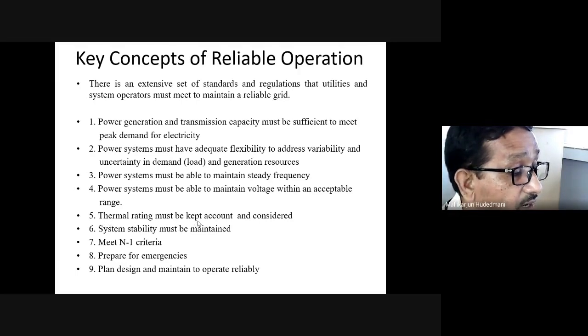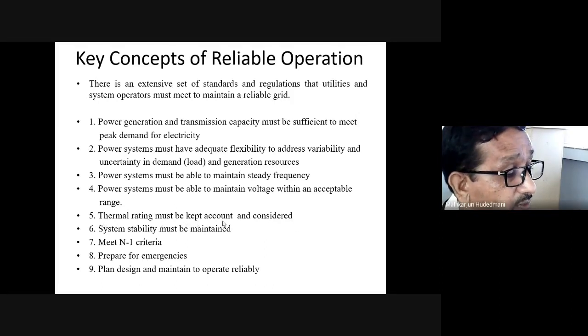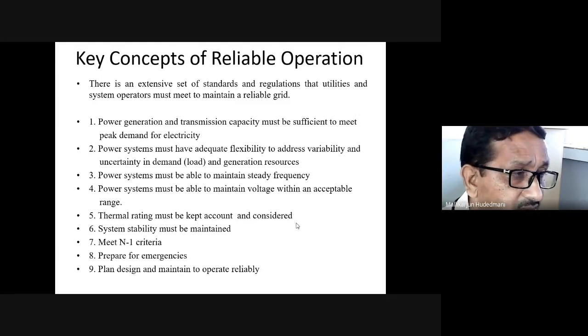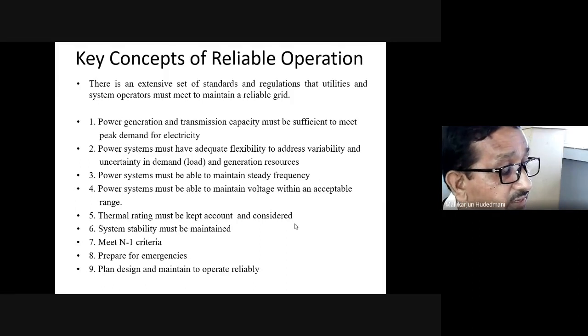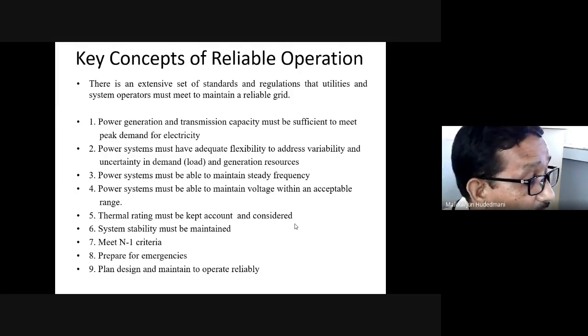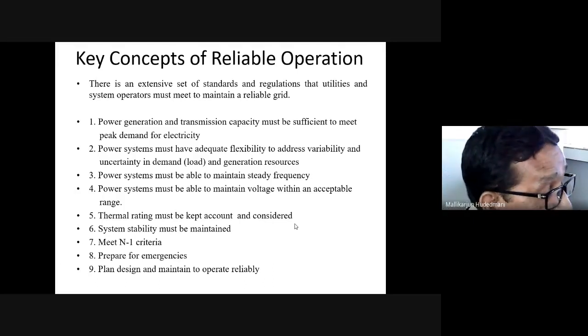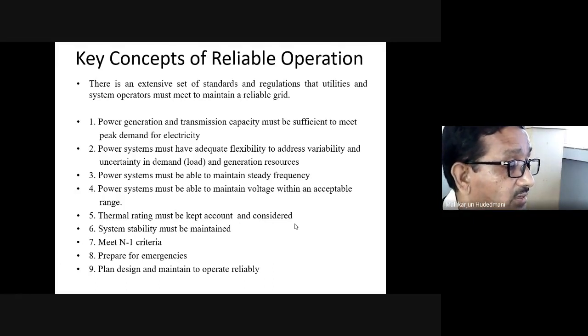For reliable operation, the thermal rating must be kept in account and considered. Look at a certain transmission line, a transmission between buses over a long distance of L kilometers. It has a certain ability to transfer MVA and a certain thermal ability. As the current flowing through it increases, the I squared R losses increase, and the temperature rise will cause thermal failure, thermal breakdown. That conducting material will not sustain further due to its thermal failure.